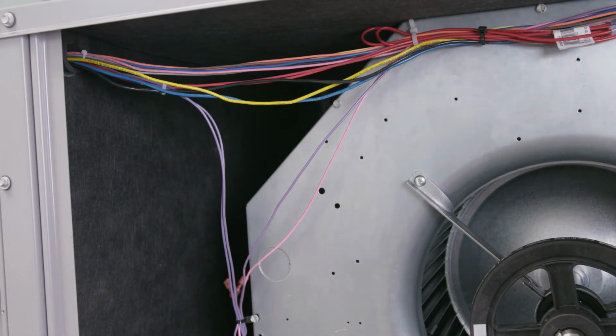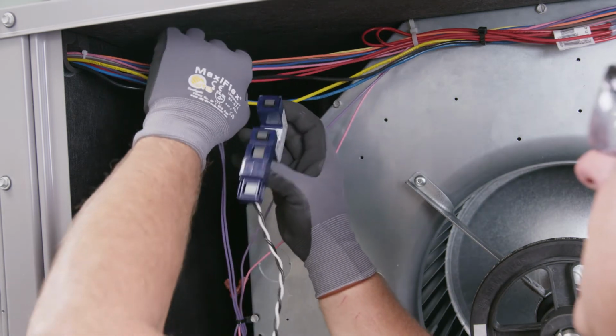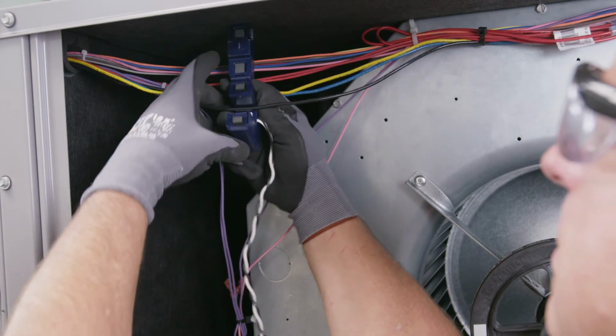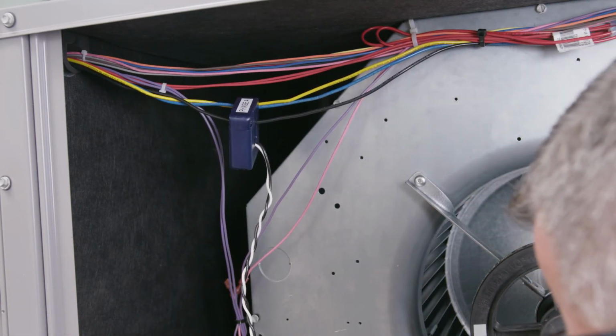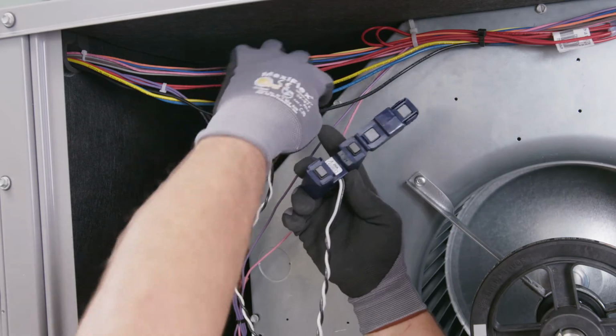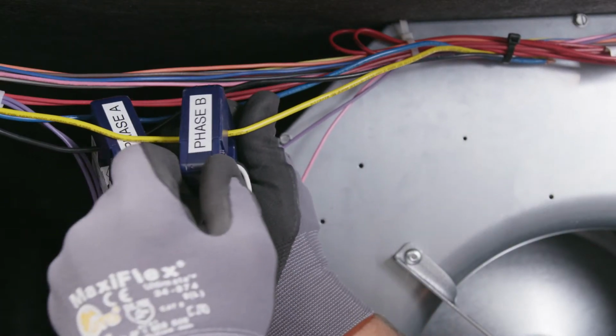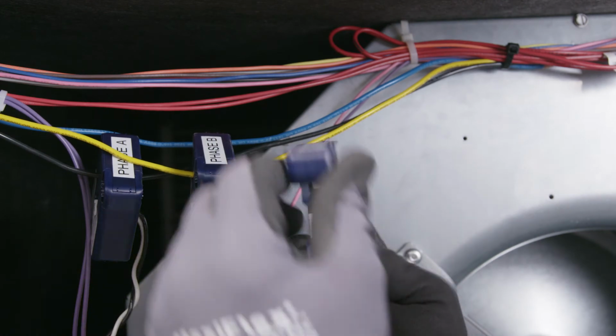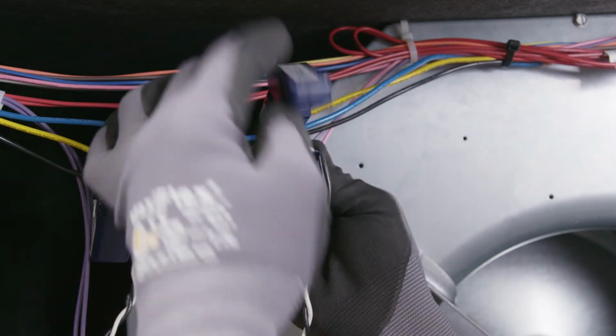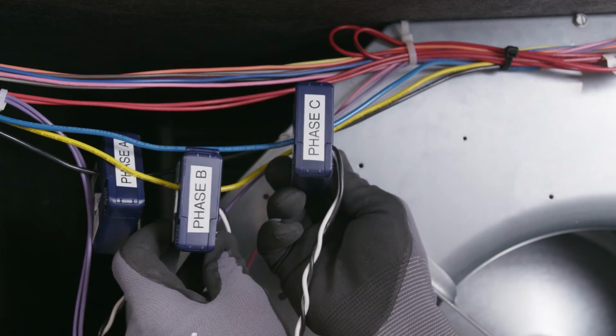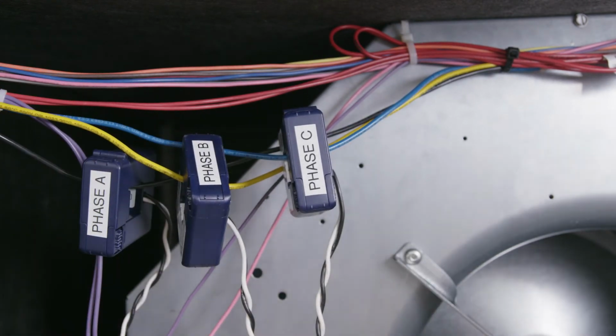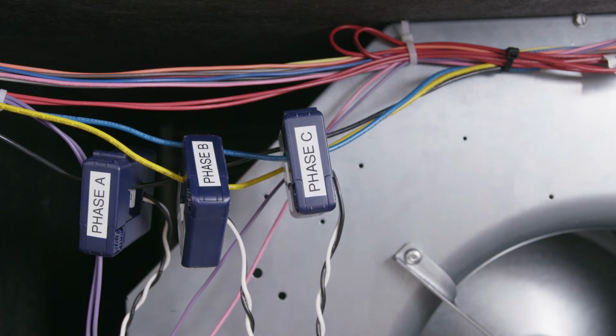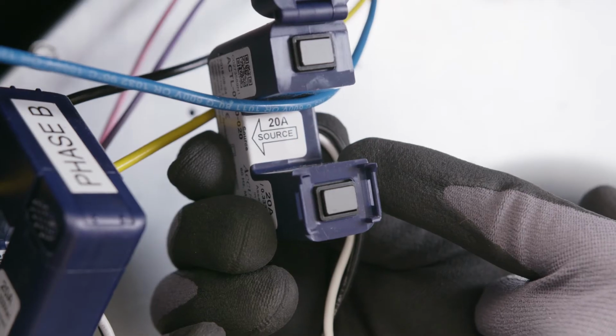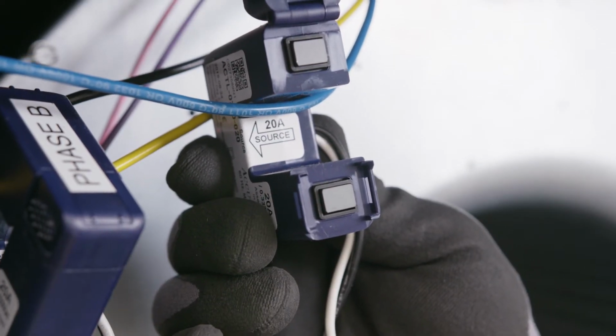Now that you've got line voltage connected to the power meter, you've got A, B, and C phase, which are black, yellow, and blue. These are the colors that the unit manufacturer uses to connect to the A, B, and C phase. Next, we're going to connect the CTs to the other side of the meter. Once you have identified the 3 line voltage wires that are going to the existing induction fan motor, the black, yellow, and blue, the next step is to install the CTs. Remember that the CTs must be installed in the same order as the A phase, B phase, and C power input to the meter. Also, please note that these CTs are directionally sensitive, so make sure that the arrow is pointing towards the power source from the HVAC unit.